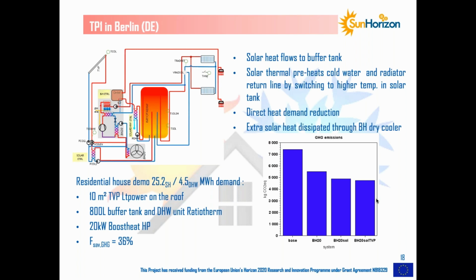That's the result for this residential building in Berlin, where the solar thermal heat classically preheats domestic hot water or the return line from the radiator of the building, in order to substitute the heat demand that is to be covered by the Boostheat heat pump. So this is a serial integration on the hot side, the heat demand side, of solar and the Boostheat heat pump.